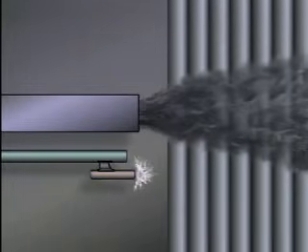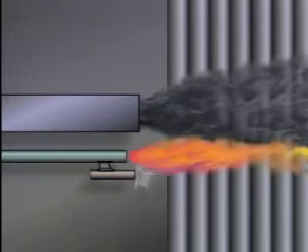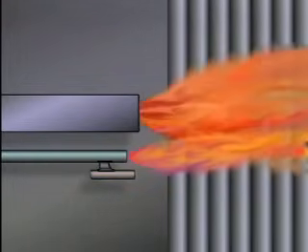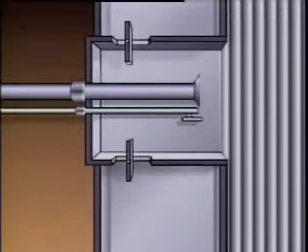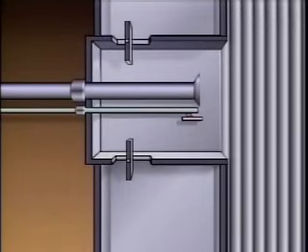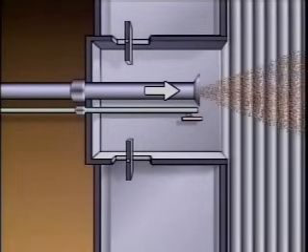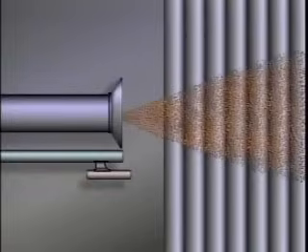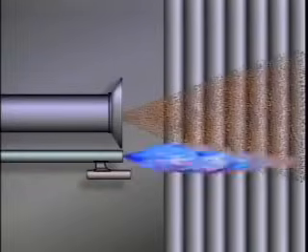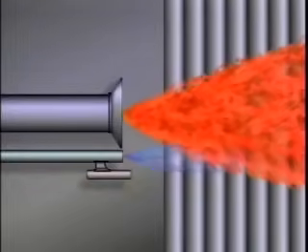The electric spark ignites the oil, which in turn ignites the pulverized coal. In one type of oil-fired boiler, oil is sprayed out through the fuel nozzle, which is designed to atomize or break up the oil into very small droplets that can mix readily with air from the air registers.